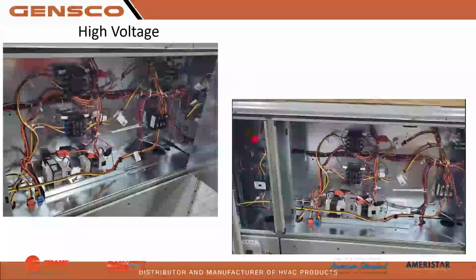Here's our high voltage panel as we open this up. Again, you can see the back side of the hinge plugs right here. It comes set up for 230. So if you have a 208 system, you will have to swap these connectors to the 208 transformer. So keep that in mind. What else we got in here? We got all of our contactors, of course, and I'll show you that phase. This one has a heat strip.